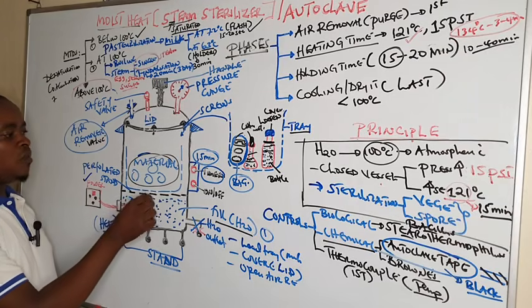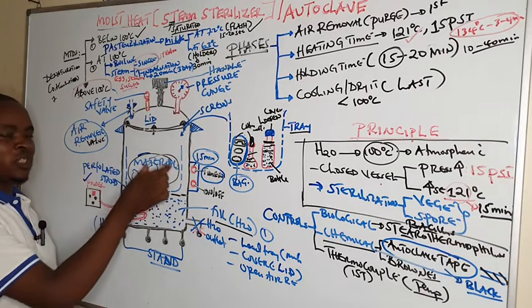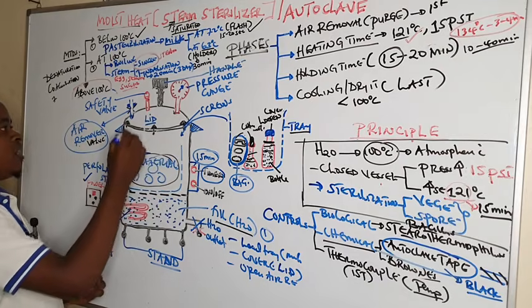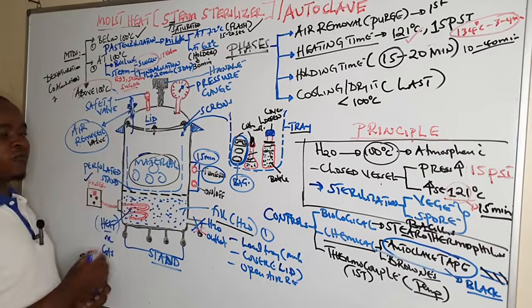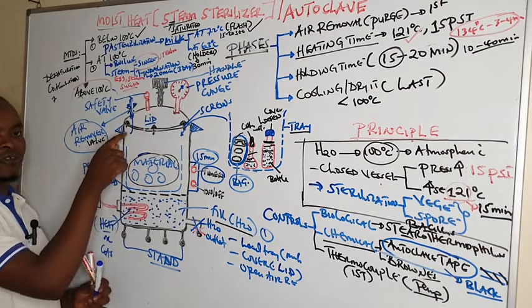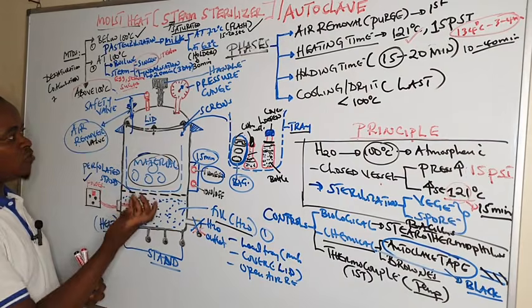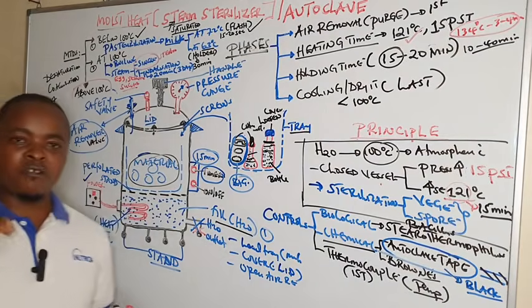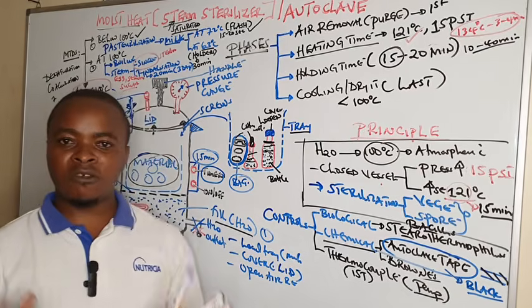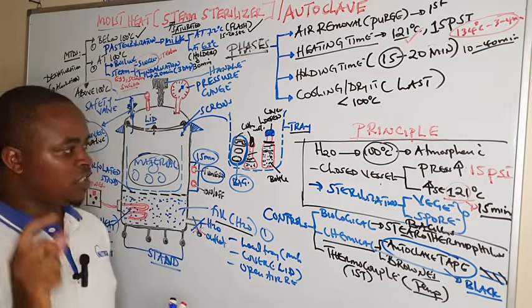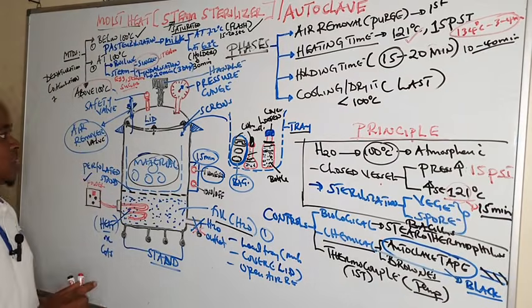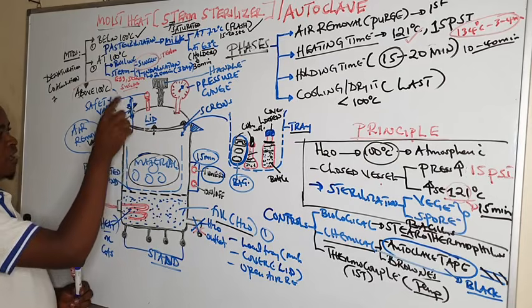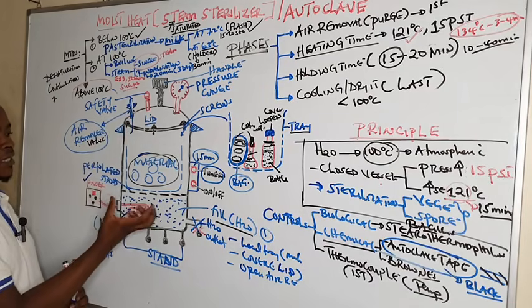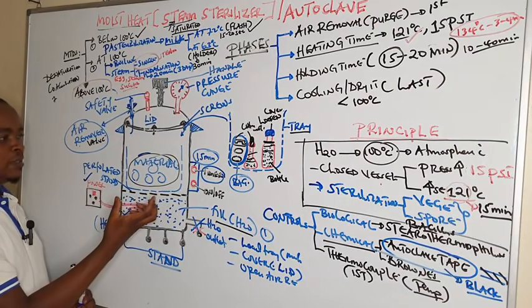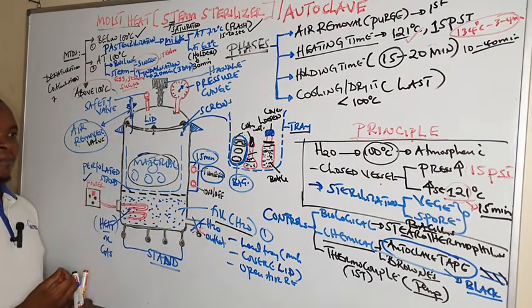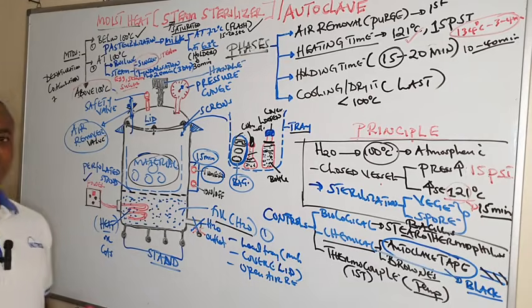And this steam will drive away all the air which was trapped in the autoclave via the air remover valve. That's why we first leave the air remover open to allow the steam to drive out the air. Because if air remains in the autoclave, it will interfere with the steam and we cannot achieve maximum sterilization. So we first open the air remover valve so that the steam which is forming from water boiling drives out the air. And how do we know that all the air has been removed?